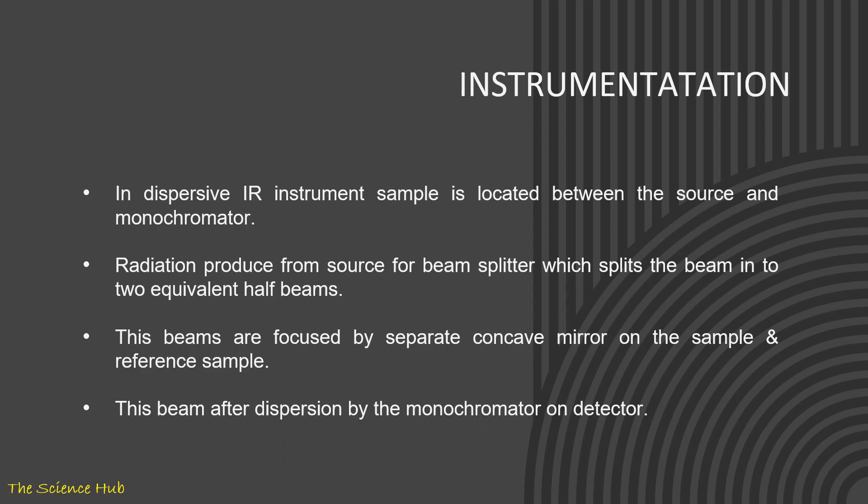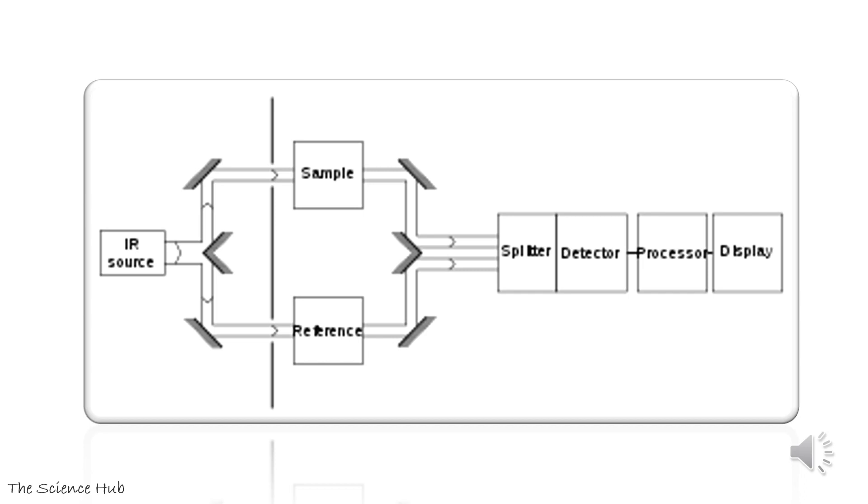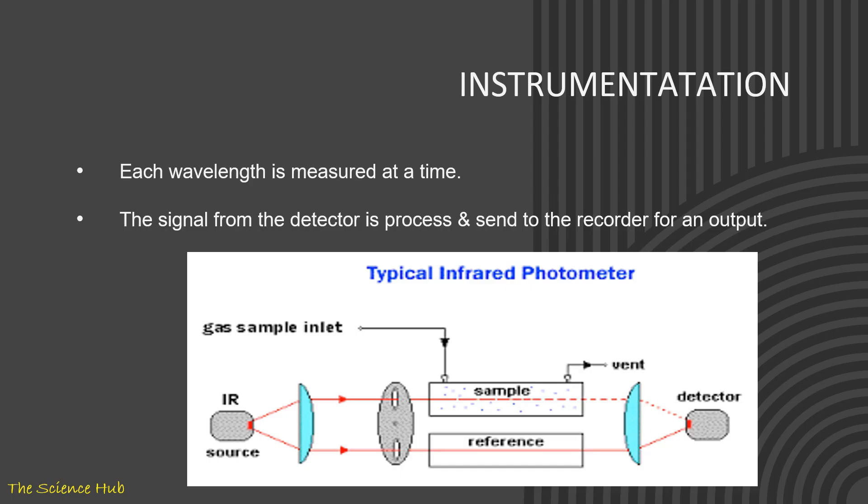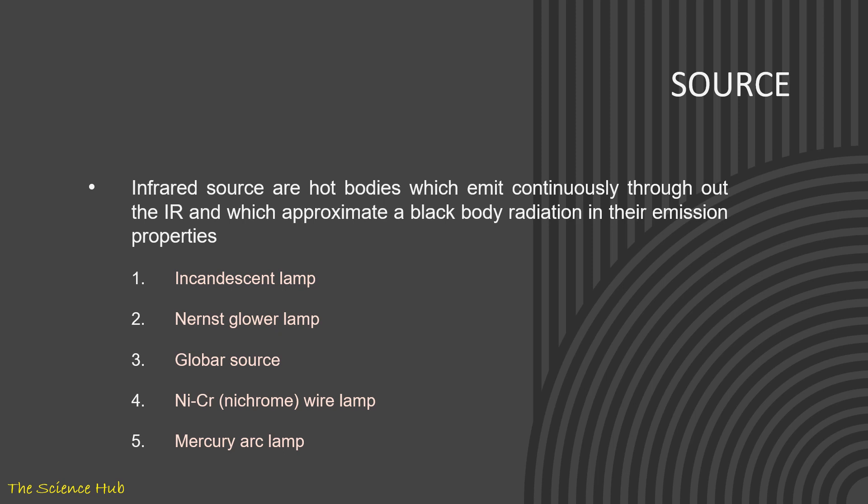Now we come to instrumentation. In dispersive IR instrument, the sample is located between the source and monochromator. Radiation produced from source for beam splitter splits the beam into two equivalent half beams. These beams are focused by separate concave mirrors on the sample and reference sample. This beam after dispersion by the monochromator falls on the detector. Here you can observe the block diagram of IR spectroscopy—double beam IR spectroscopy. Each wavelength is measured at a time. The signal from the detector is processed and sent to the recorder for output.